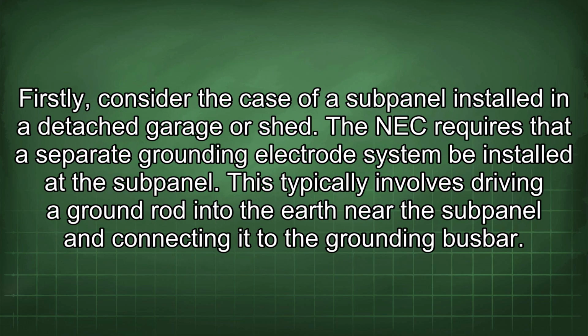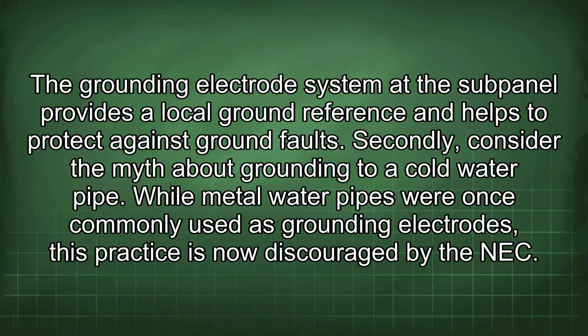Firstly, consider the case of a subpanel installed in a detached garage or shed. The NEC requires that a separate grounding electrode system be installed at the subpanel. This typically involves driving a ground rod into the earth near the subpanel and connecting it to the grounding busbar. The grounding electrode system at the subpanel provides a local ground reference and helps to protect against ground faults. Secondly, consider the myth about grounding to cold water pipe. While metal water pipes were once commonly used as grounding electrodes, this practice is now discouraged by the NEC.